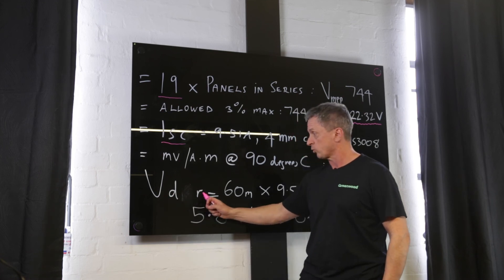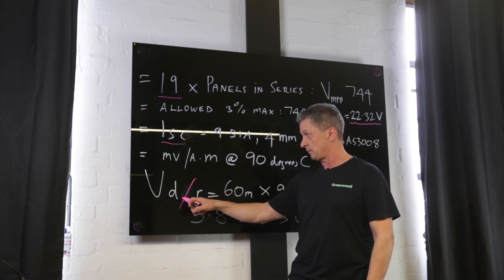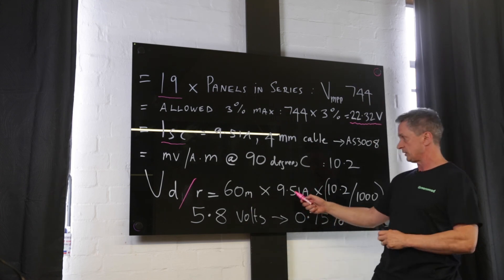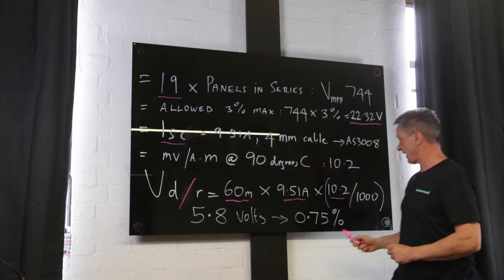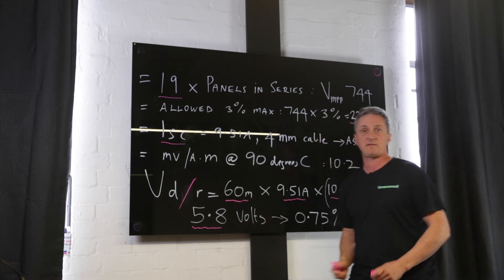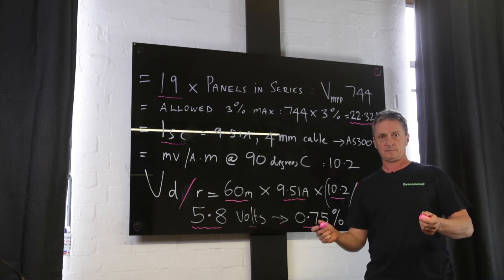So the Volt Drop — remember Volt Drop and rise are the same mathematically, it just depends on what you're trying to ascertain. We have a 60-metre run, a single string at 9.51 amps, and a millivolt per amp metre factor of 10.2. Taking that over a thousand gives us 5.8 volts of Volt Drop, which is 0.75% — well under the 3% maximum. Thanks very much for watching our presentation on DC Volt Drop calculations — a very important area that many installers don't look at closely. Please subscribe.